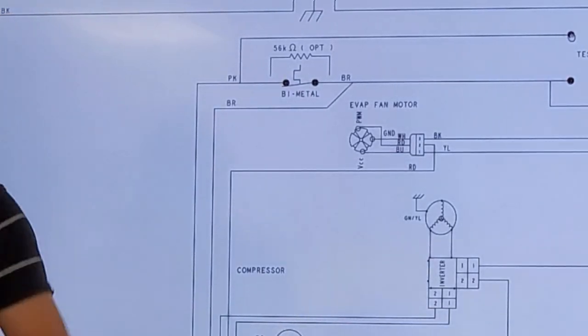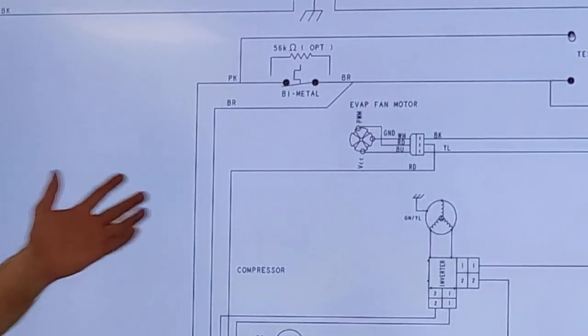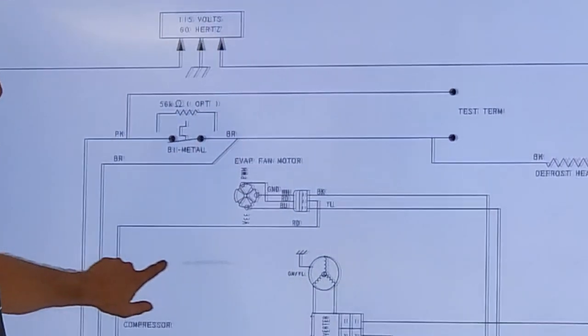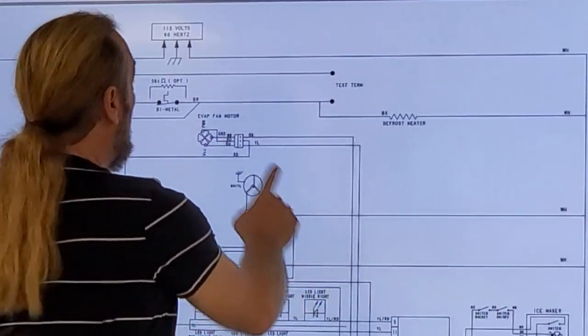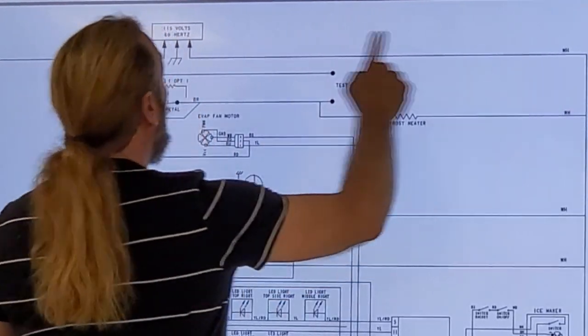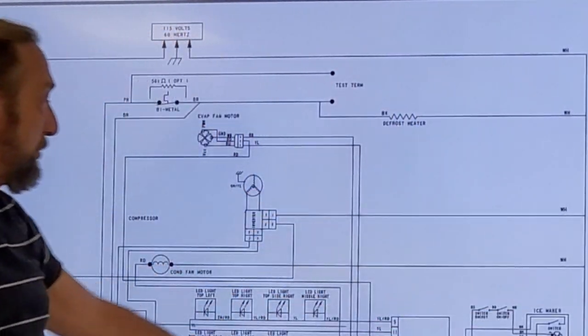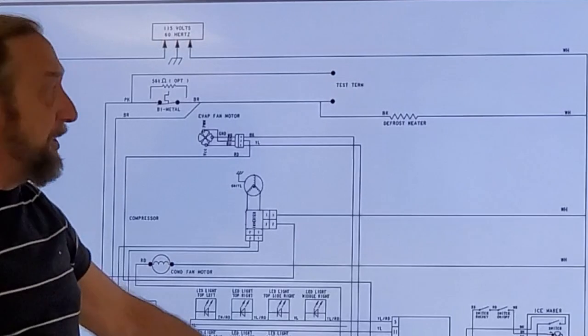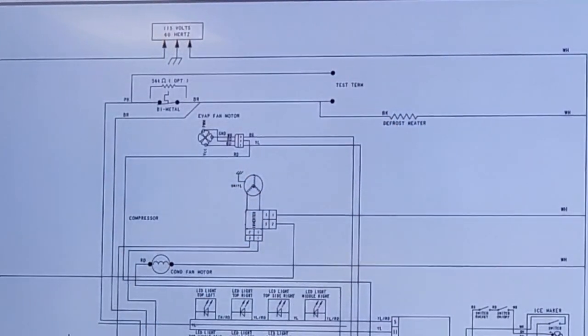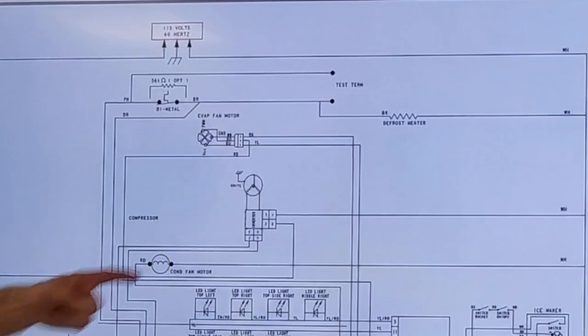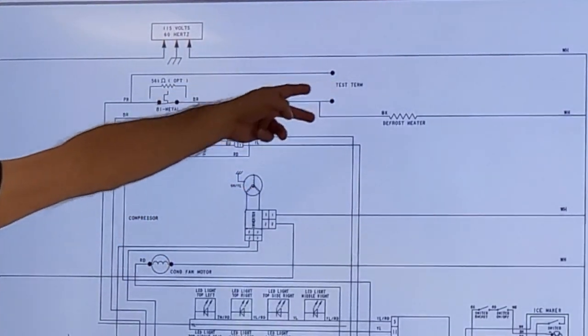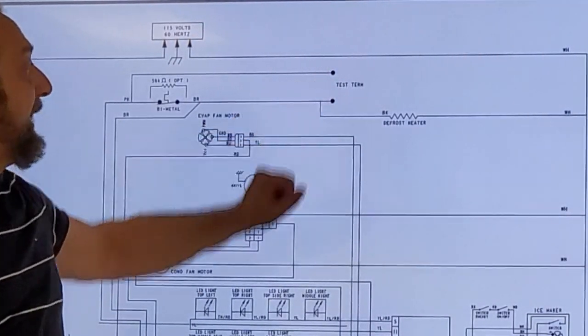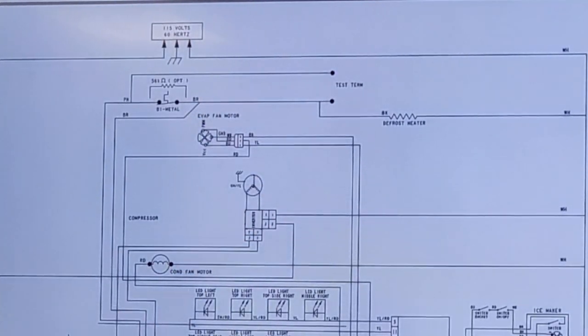So you can see here all these LED lights — that has a driver. What does that mean? Power. So if we wanted to check voltage, we could go to the board here — here's the LED driver. It tells you 115 going in and 14 coming out. So this driver — two of those wires are 115 volts coming in, and the rest are 14 volts coming out. If the lights aren't working, you know you've got 14 volts coming out — it's not the board, it's something with one of those lights.